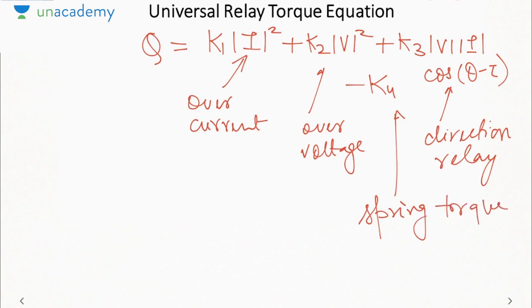Okay. Now, any of these terms can act as operating torque or as a restraining torque. But it might be confusing for you, since I have included only one negative term. How can any of these terms behave as a restraining torque? Because net torque is always operating minus restraining. So restraining torque must come with a negative sign. The thing is that whenever any term will be taken as restraining torque, by default we will put a negative sign before that, so that it will act as a restraining term and the other term will act as an operating term. Other thing to remember is all these terms will not appear in all the relays.